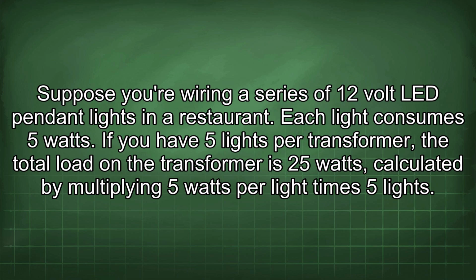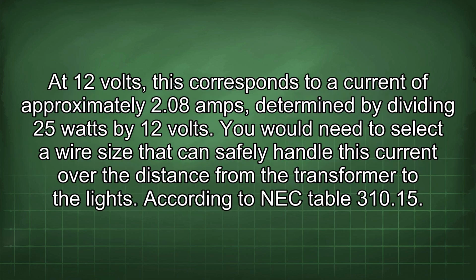If you have 5 lights per transformer, the total load on the transformer is 25 watts, calculated by multiplying 5 watts per light times 5 lights. At 12 volts, this corresponds to a current of approximately 2.08 amps, determined by dividing 25 watts by 12 volts.